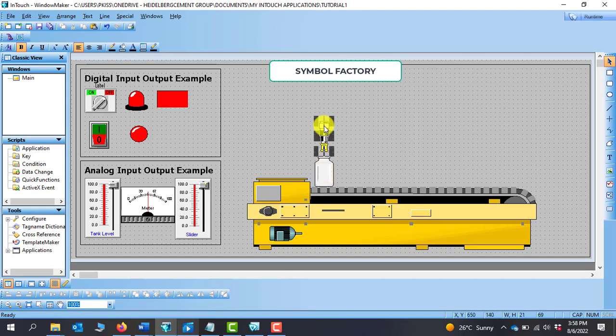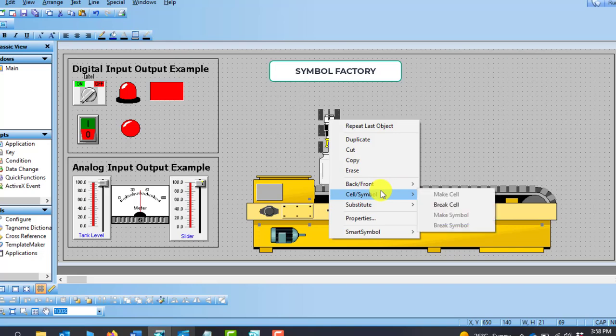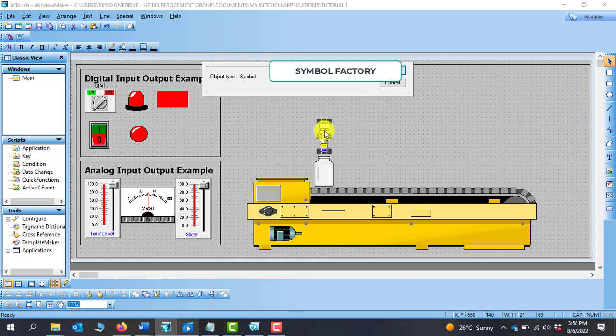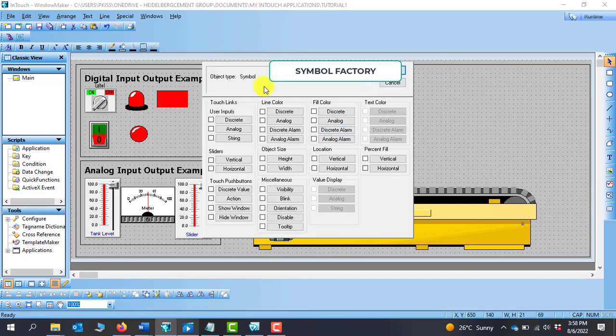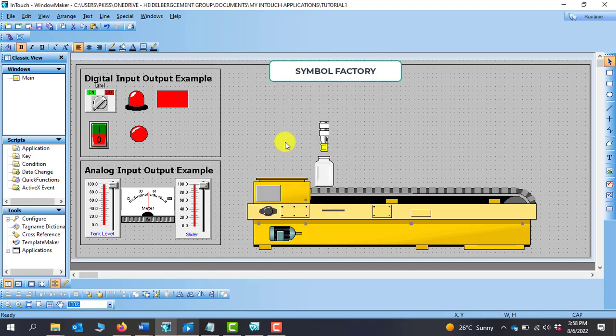So how can we apply properties to Symbol Factory items so we can make them blink or change states? To do this, right-click and go to Cell Symbols, then go to Break Cell. Immediately you click Break Cell, the symbol will be broken and you'll be able to access the animation properties — color, fill, text, object, and locations — so you can apply movement to it.